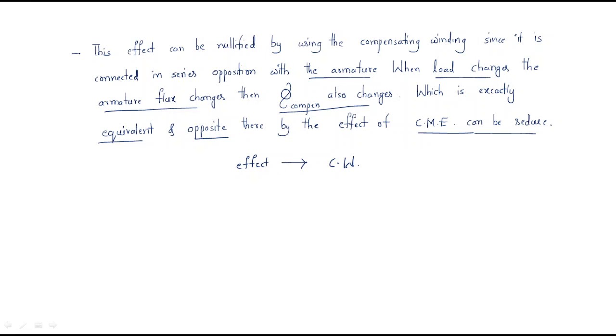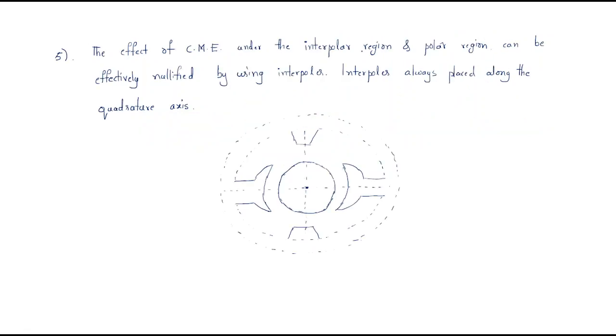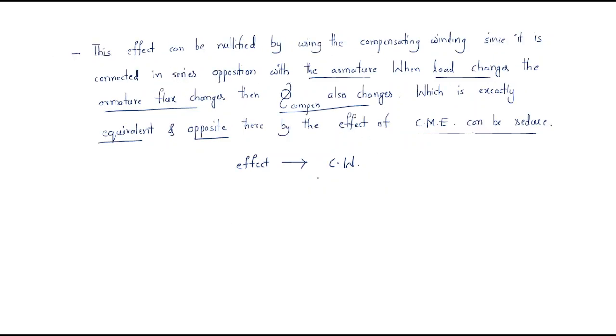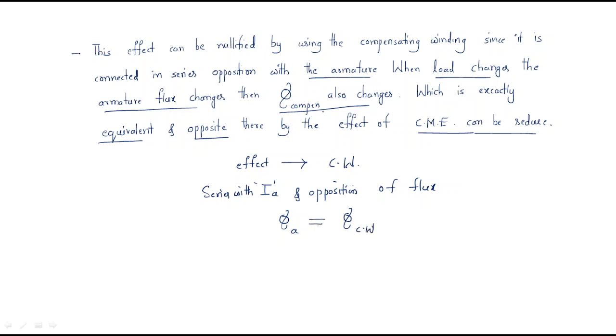The compensating winding is connected in series with the armature current and in opposition of the flux. Therefore, the flux due to the armature and the flux due to the compensating winding are both cancelled, since they are exactly opposite and equal. As a result, the cross-magnetizing effect (CME) can be reduced.